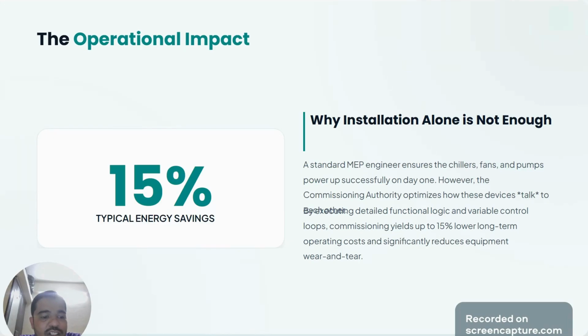A site engineer might turn on the chiller, verify it gets cold, and check the box, but the CxA spends hours calibrating the exact logic loops, making sure the sensors are perfectly aligned, valves close fully when they're supposed to, and the fans don't run at 100% capacity when the building is empty.